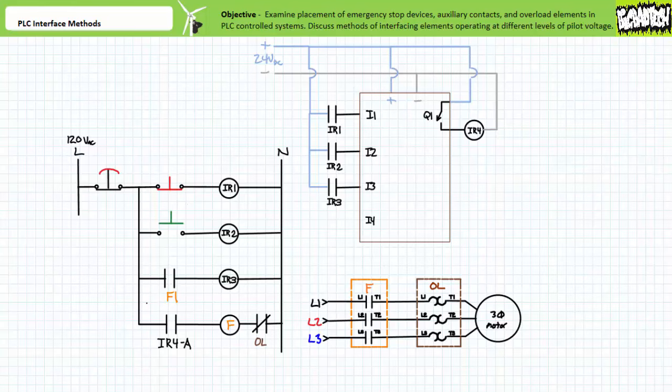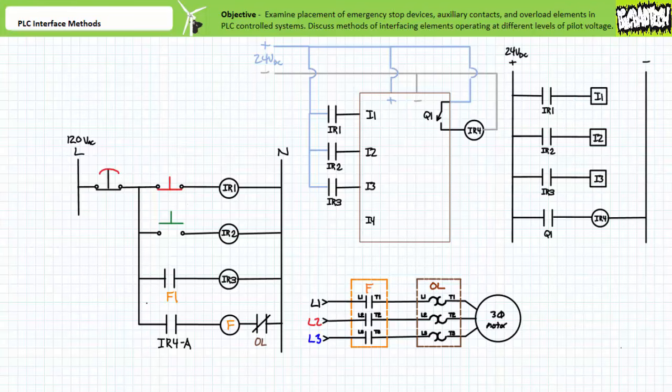Used in this manner, the interposing relays are in effect acting as messengers between the field input-output devices and the PLC operating at different voltage levels. While a somewhat indirect and inelegant game of telephone is being played using this methodology, it does allow for ordinarily incompatible devices to play nice together and accomplish some larger task. Adding interposing relays to a PLC only slightly complicates the schematic representation.